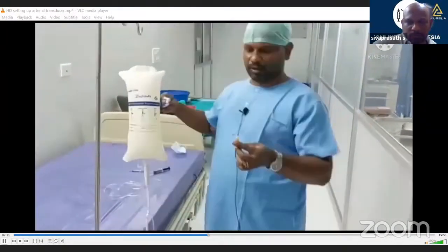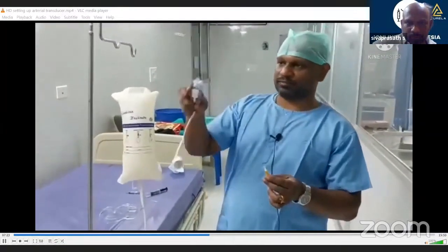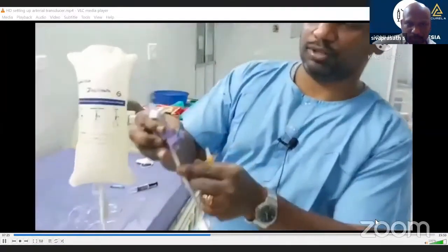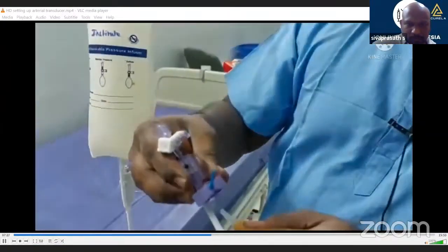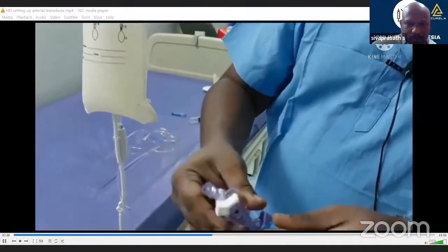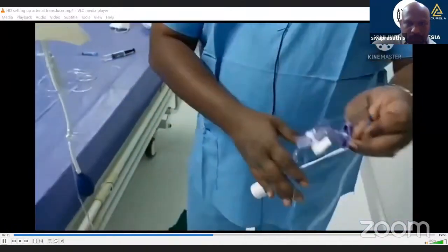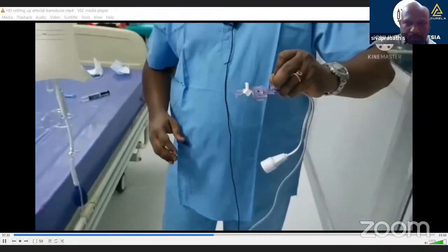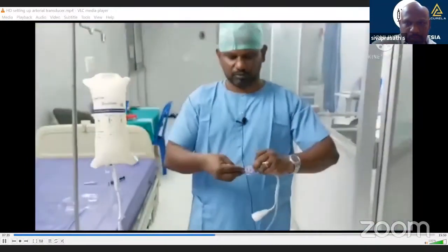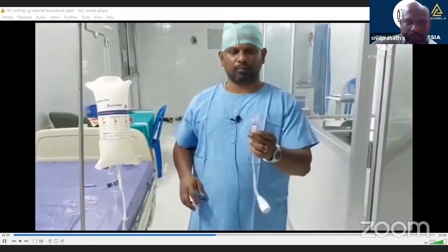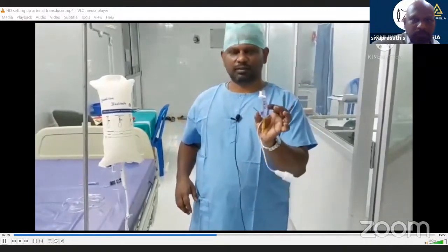And now I'll have to connect my transducer's flush end. I've already told you this is the flush end, to this flush system. And if I slightly open this, automatically all the air in the system will come out. So it has all come out. So completely my flush system has de-aired the transducer.